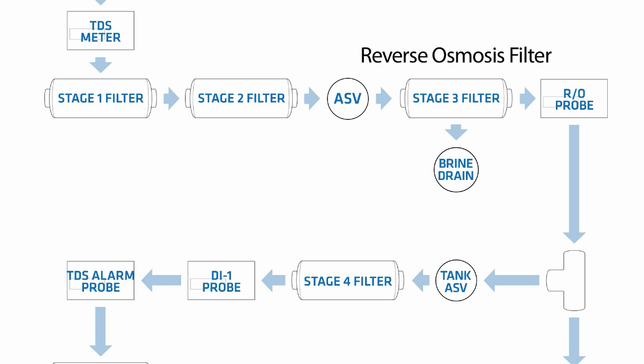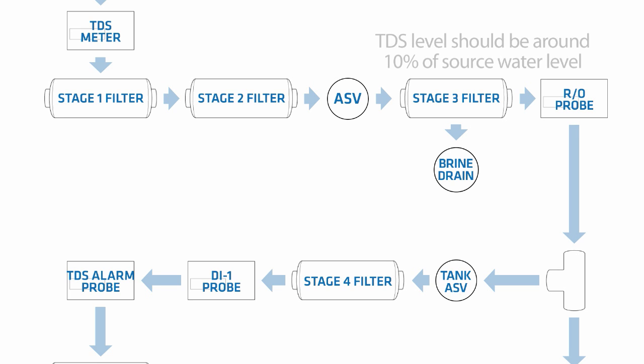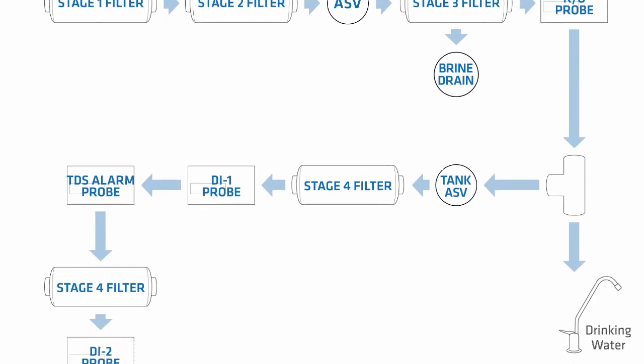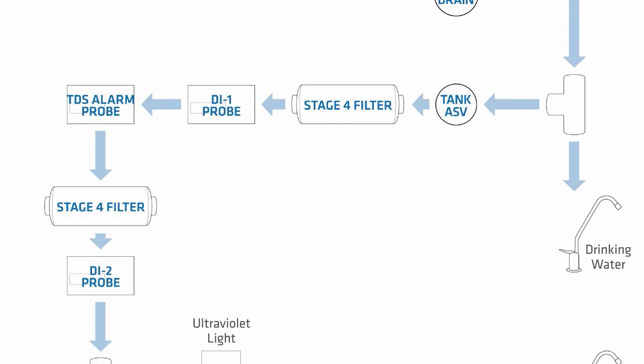Stage 3 is a reverse osmosis filter. Water moves through a semi-permeable membrane and contaminants from the water are drained via the brine drain at the bottom of the Stage 3 cartridge. Ideal readings for the RO monitor should be around 10% of the source water reading. From there, the water passes the reverse osmosis probe to determine the water hardness after Stage 3. Then the water flows into a T connection, with one side going to the drinking water output and the other side continuing through the automatic shutoff valve for the tank and into the first Stage 4 deionization filter.